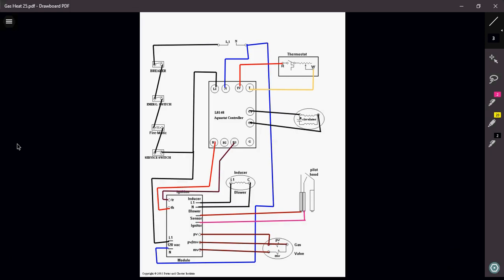My inducer motor will now start to spin so that I can clear out the flue pipe and combustion chamber inside the boiler of any toxic and possibly explosive gases that may still be sitting in there from the last ignition sequence. Once that happens and everything is proved, there would probably be a vent pressure switch of some sort to prove that the inducer motor started to spin and is in fact clear.